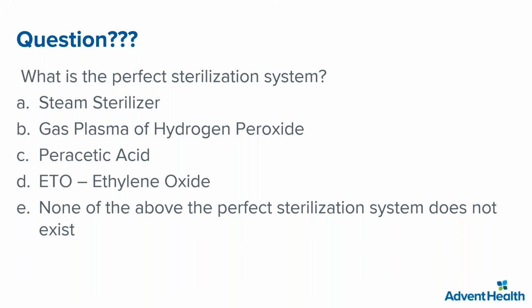Okay, yes, it's E. You know why? Because there is no perfect sterilization system. We have steam for instruments that can withstand heat. We have gas plasma of hydrogen peroxide or peracetic acid for delicate instruments at temperatures less than 50 degrees. I put ETO. ETO is ethylene oxide, a gas, but it's no longer used because it is carcinogenic, and it works the same way. However, ETO takes about 8 hours to run a load. So the answer absolutely is E. None of the above. The perfect sterilization system does not exist.